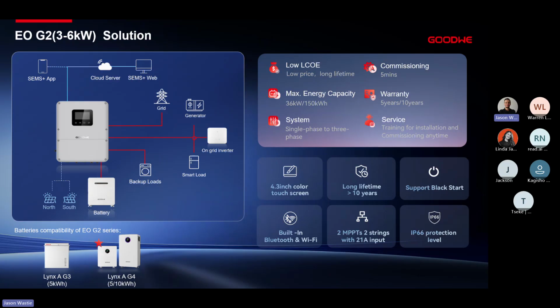When our batteries are full, allow our backup loads and our normal smart loads to run. And when the battery reaches a lower SOC, turn off our smart load and allow only our backup loads to run. So nice in an off-grid application where we know how much PV we can generate in a day, and we obviously want to be able to handle all of our loads at one time, and when we can't handle all of the loads, turn off some and allow the rest of our system to work until the next day when we've got enough PV again to charge our batteries up.